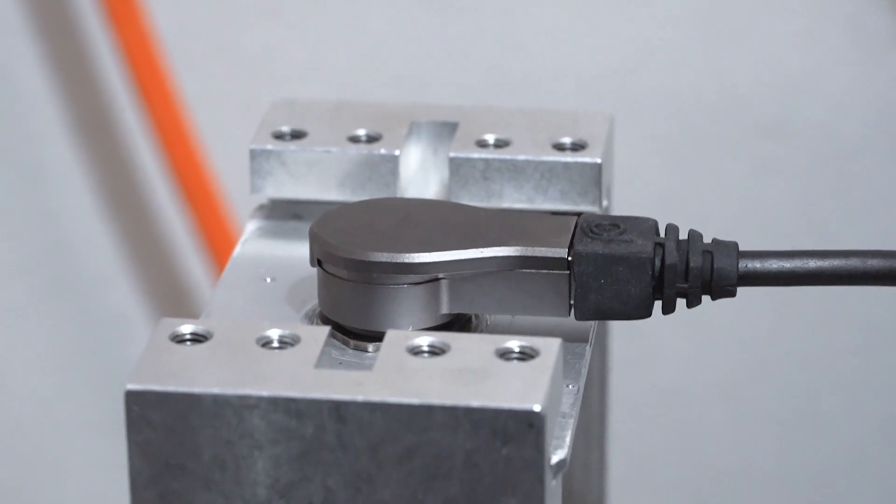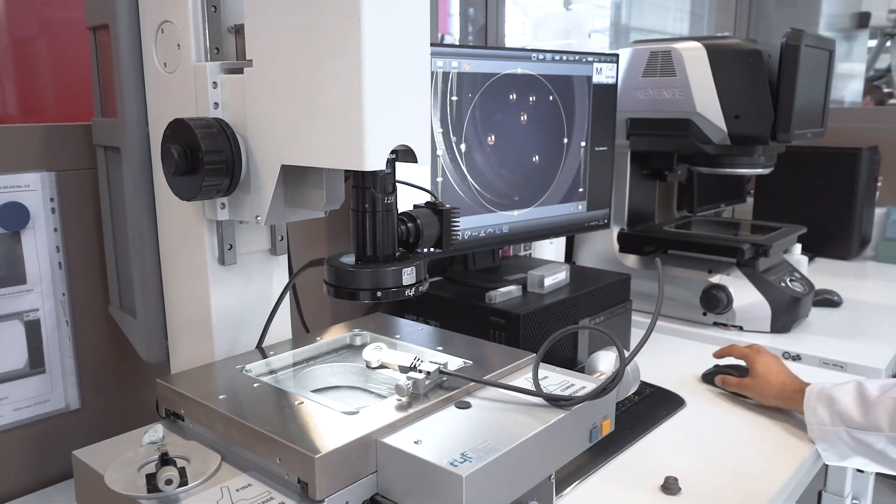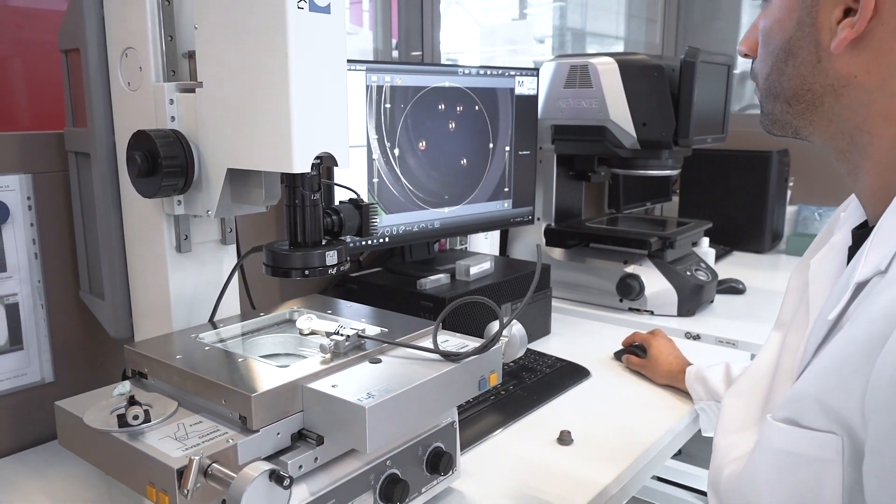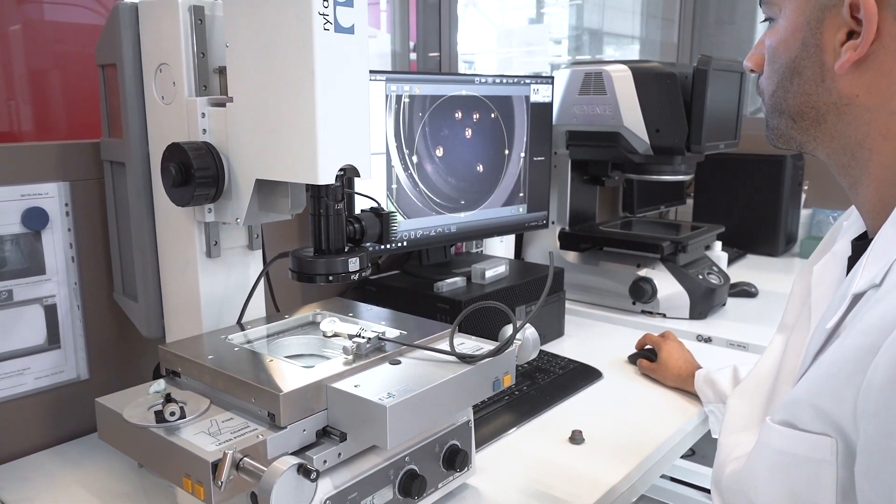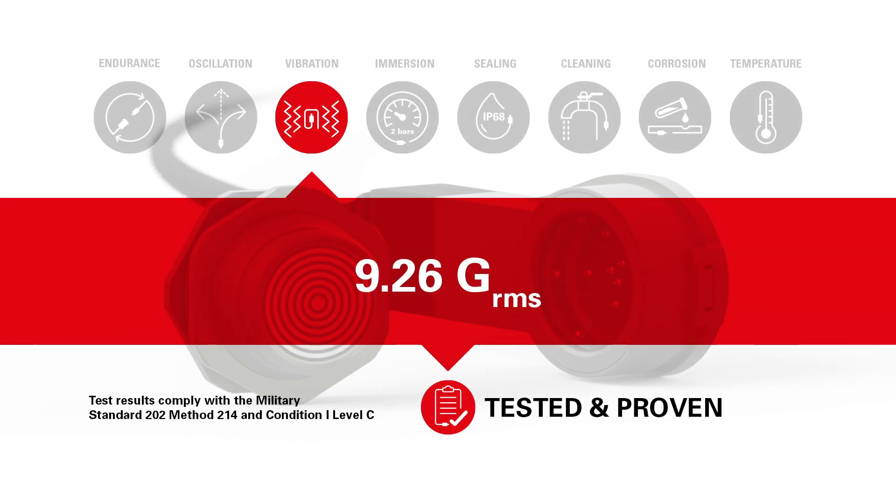Locking system and contacts are inspected using a high-performance optical microscope. During both tests, electrical signals are monitored to ensure that no microcuts smaller than one microsecond can occur.